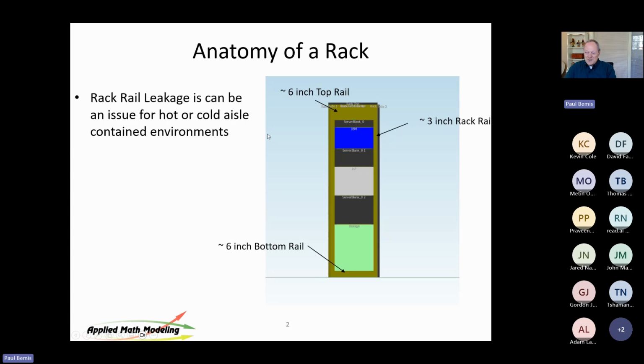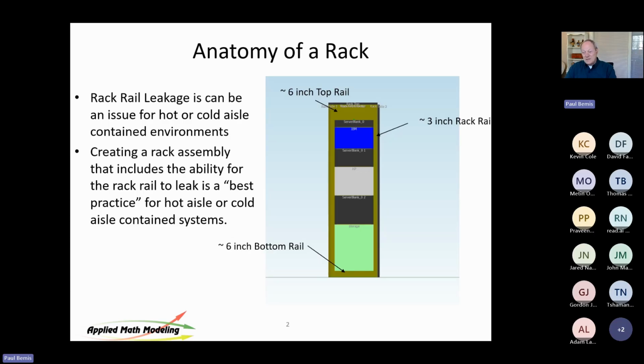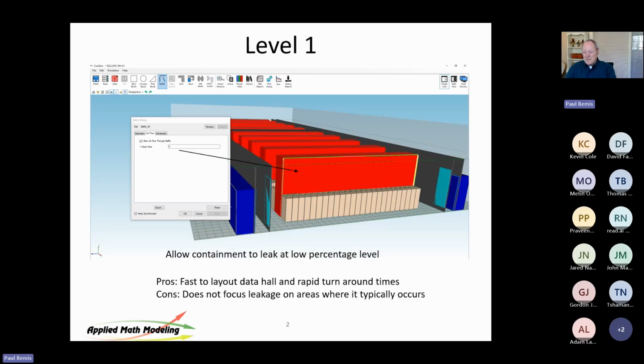So rack leakage can be an issue for hot and cold aisle containment. It usually is the issue. And you can create a rack assembly that is best practice for hot and cold aisle systems. You can build each one of these out of CoolSim using an assembly. But let's go through more of a practical approach of how you do it in CoolSim.